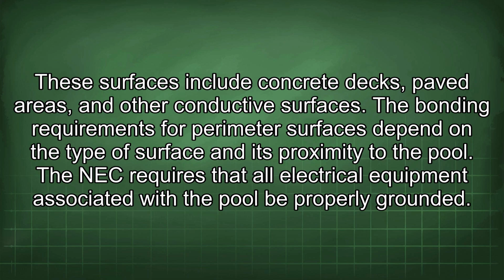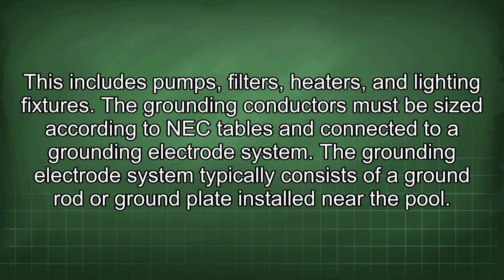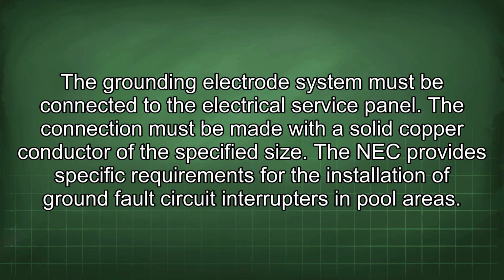The NEC requires that all electrical equipment associated with the pool be properly grounded. This includes pumps, filters, heaters, and lighting fixtures. The grounding conductors must be sized according to NEC tables and connected to the grounding electrode system. The grounding electrode system typically consists of a ground rod or ground plate installed near the pool. The grounding electrode system must be connected to the electrical service panel. The connection must be made with a solid copper conductor of the specified size.